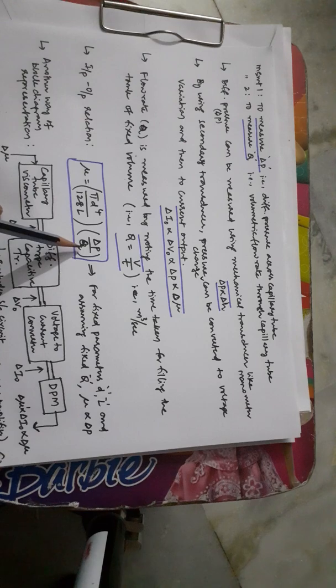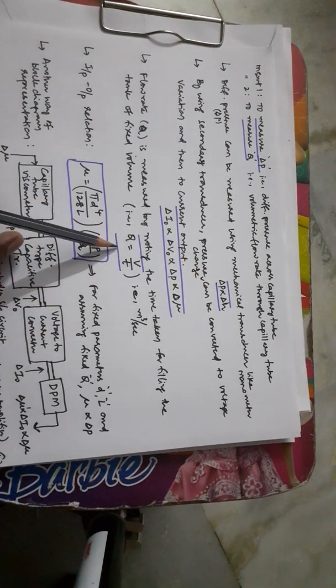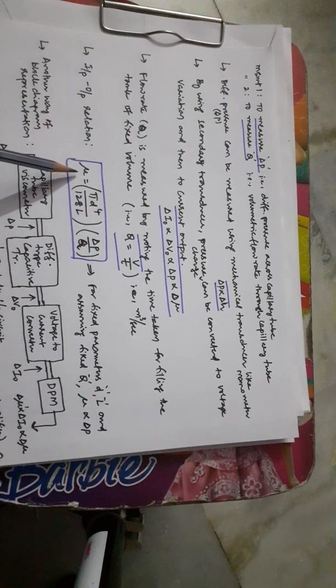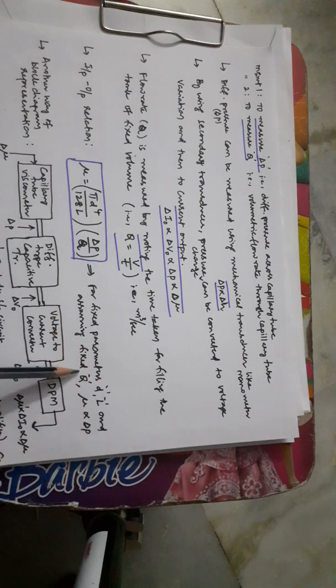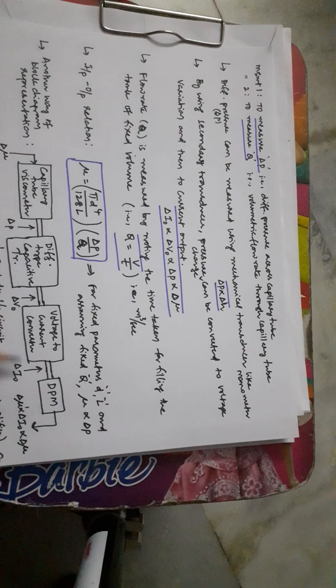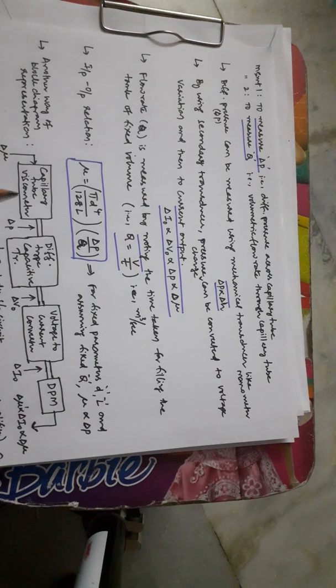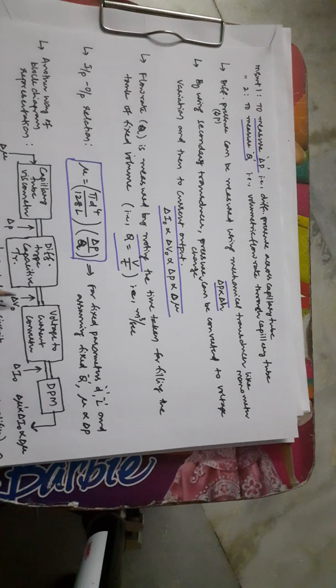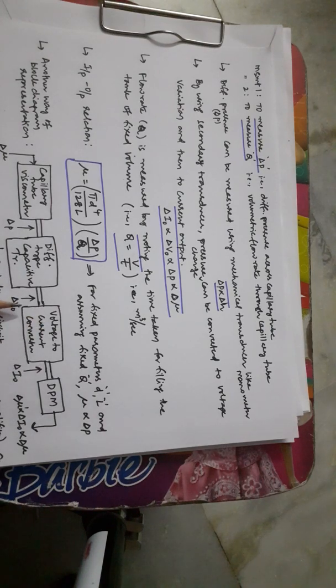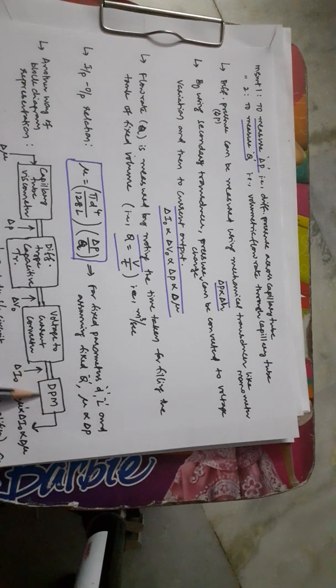Substituting the measured delta P and Q into the input-output relation gives the viscosity. For fixed parameters D and L, and a constant Q, mu is proportional to delta P. A more detailed block diagram for the electrical transducer shows: first block — capillary viscometer converting viscosity energy to pressure energy; second block — a differential-type capacitive transducer converting pressure energy to electrical energy as voltage; third block — a V-to-I converter; and finally a digital panel meter displaying calibrated values delta mu.